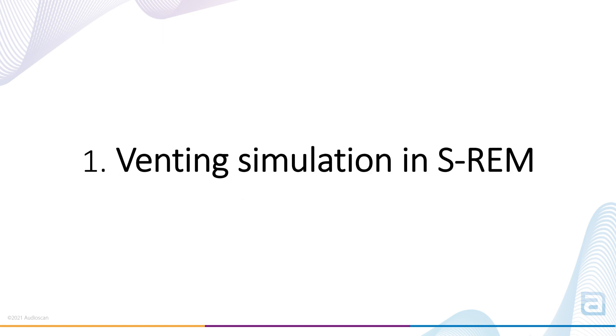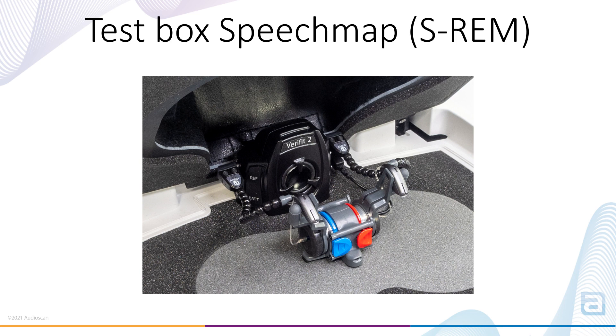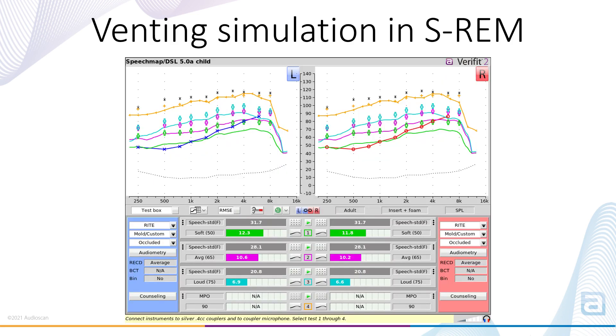Venting simulation. Simulated real ear measurements in the test box have been available in the AudioScan equipment for decades, but there was always a limitation when it comes to accurately simulating the vent effects associated with more open fittings. With this new feature, on-ear effects of venting can be simulated when running speech map tests in the test box to provide an improved prediction of in situ performance. When in test box mode, the speech map interface in the Verifit 2 and Axiom now includes two new pop-up menus so the clinician can select the appropriate venting configuration.